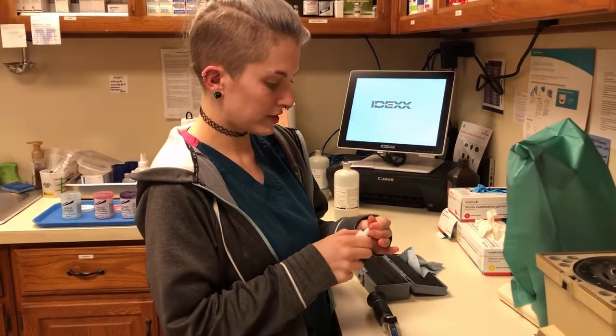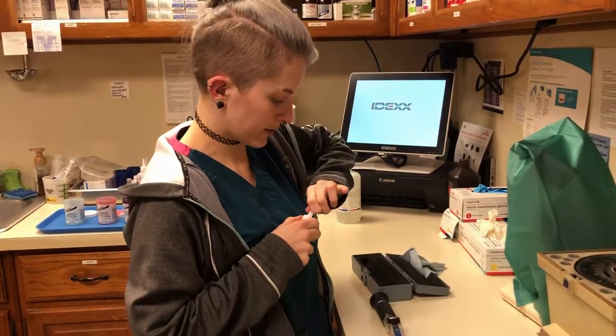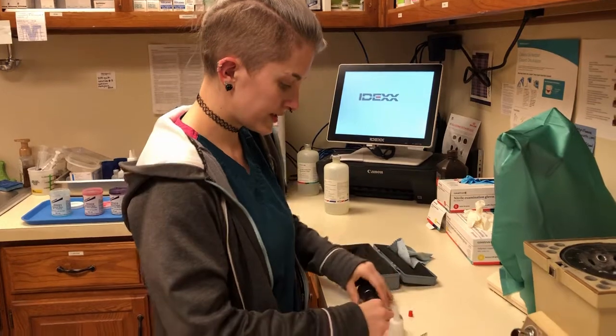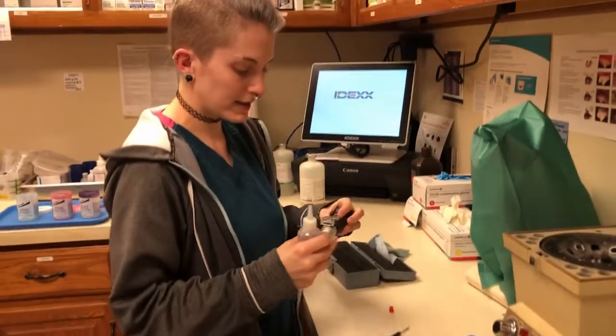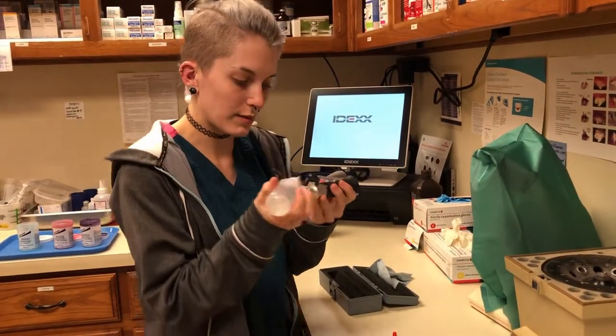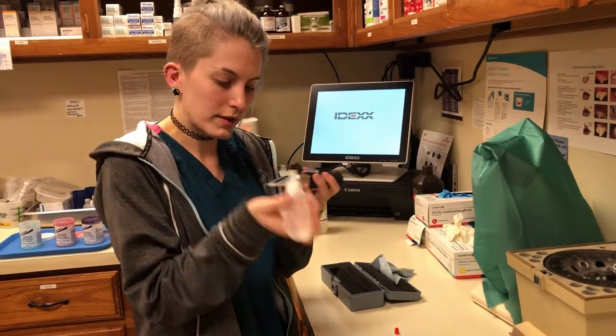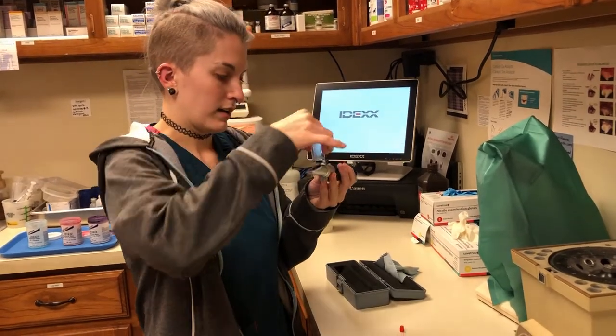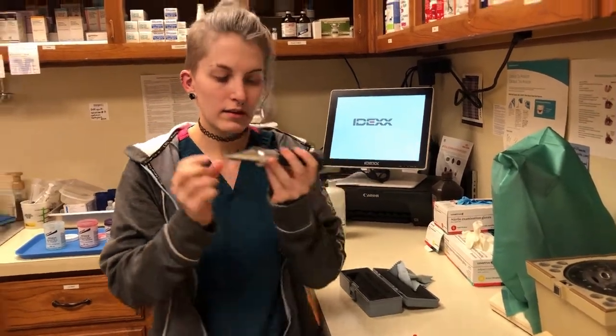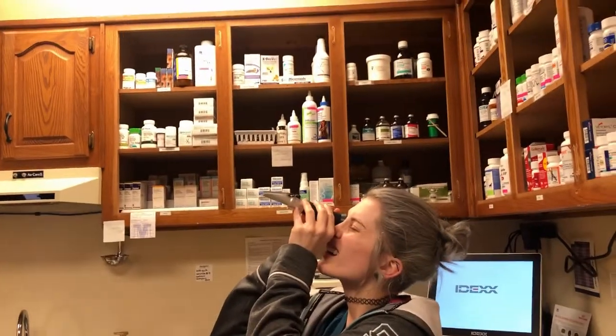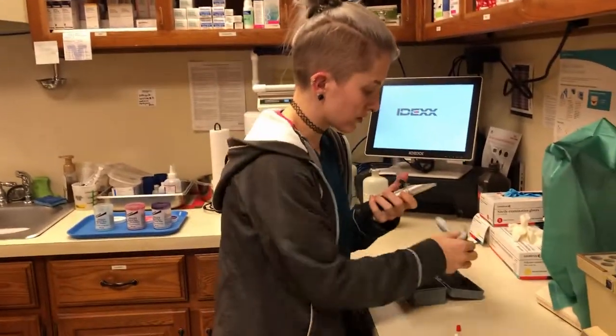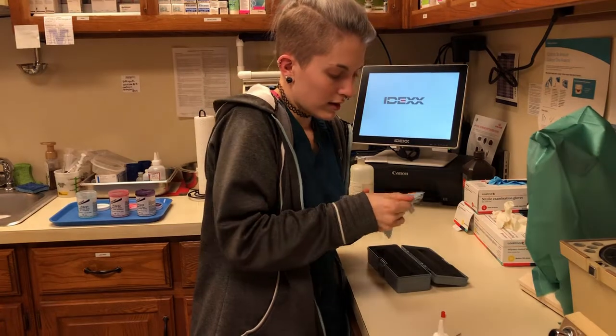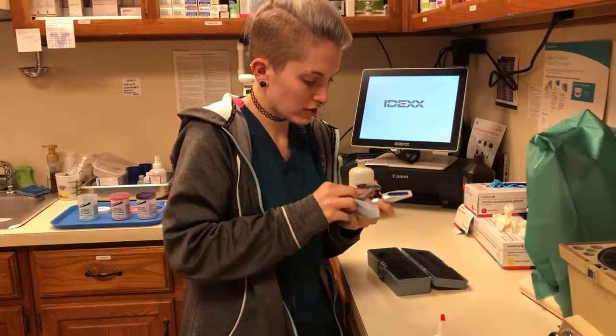All right, so we are going to check the calibration for our refractometer. What you need to do is take plain distilled water, and we're just going to put 1 drop onto our prism screen and check. Let's see, I need a smaller drop.